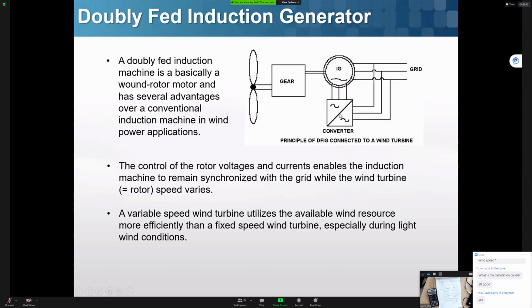We first use this converter, which is more like a VFD. Some of you learned VFD in third year, some of you didn't. It first has a rectifier part to change this AC into DC. Then it inverts this DC back into AC at a different voltage and different frequency. This is connected onto the rotor winding. So by feeding a different voltage and frequency into the rotor winding to match the rotating speed of the rotor, we can always generate 600 volts and 60 hertz at the stator part. That's what we call the doubly fed induction generator. They have a pretty high efficiency.